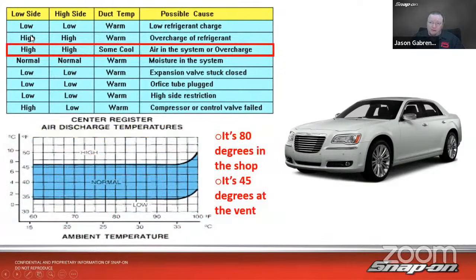So it's high, some cool, air in system or overcharge, because if we look at the ambient temperature chart, at 80 degrees ambient and 45 degrees out of the vent, that is just at the very top of what normal is. As we get over 100 degrees, it goes higher. But in this range, we should be lower than this. We're right at the very top of that range. If we cooled down even 5 more degrees, we'd be right in the middle of normal. So 45 degrees at the vent is a little bit cool, but it's not cool enough. Air in system or overcharge.